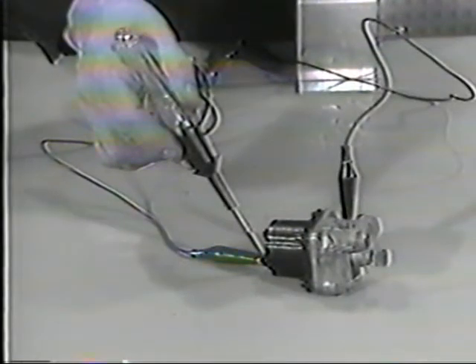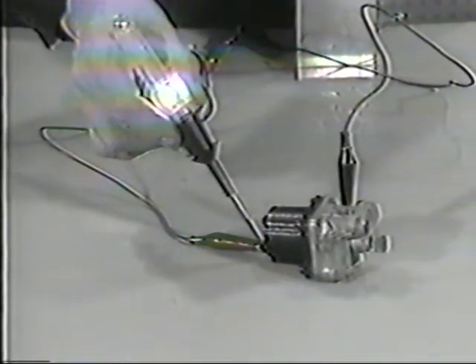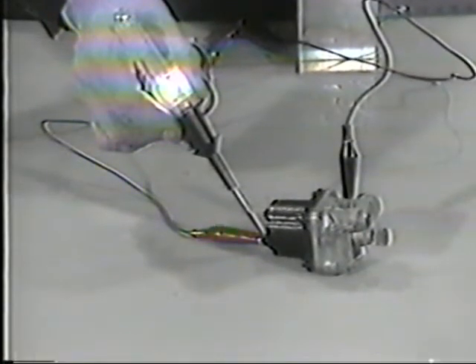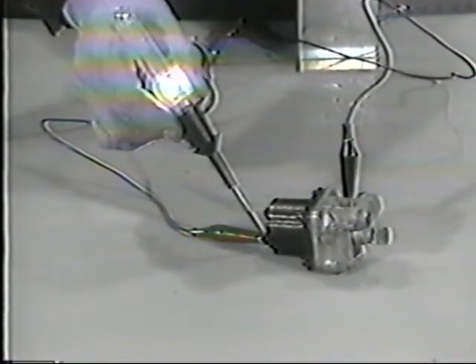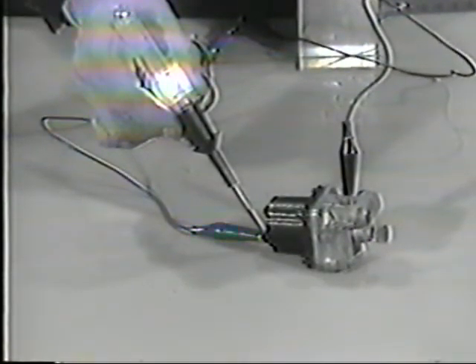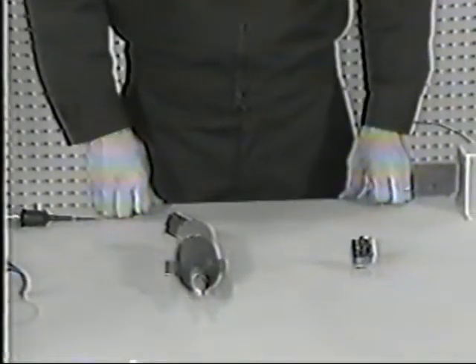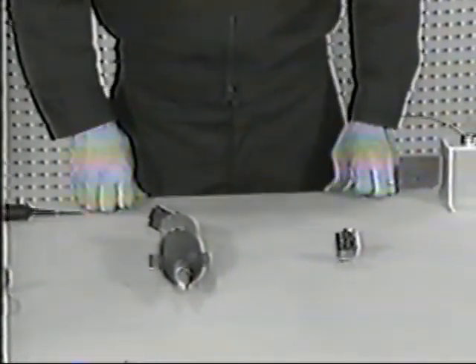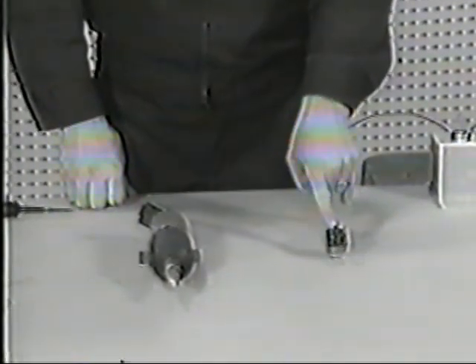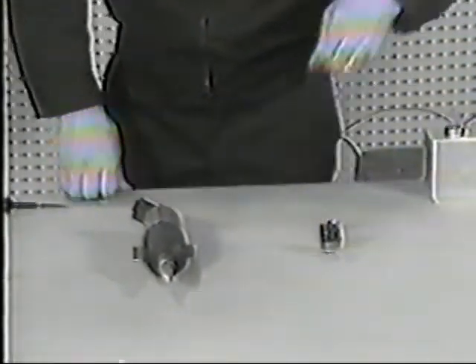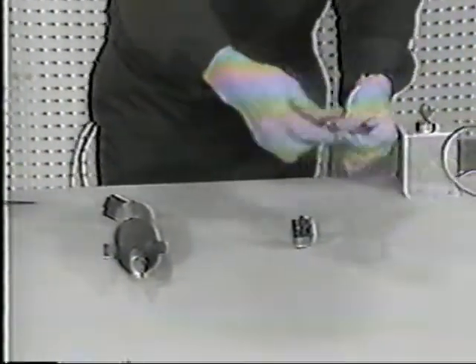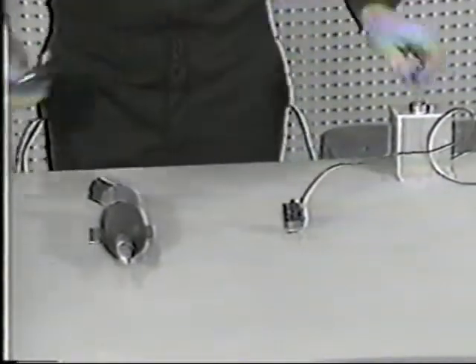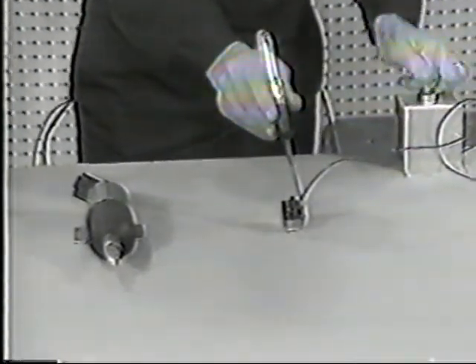On other installations, we have a fuel solenoid. When the key is turned on, voltage operates the fuel solenoid, which turns the fuel on, and the engine can be run. This type of fuel solenoid can be used with KYSOR shutdown systems as long as it does not require more than 3 amps to operate it as part of a 12-volt system. This is another type of fuel solenoid. It is quite large and requires well over 3 amps to operate it. Because of that, we cannot wire it directly like we saw with the first two. We must use a relay between the fuel solenoid and the shutdown system. We'll begin by connecting the key switch run wire to this terminal on the relay, so that whenever the key switch is on, that terminal is hot.